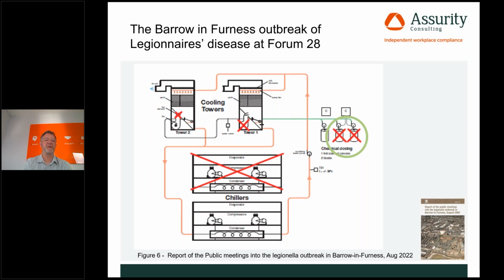As far as the two cooling towers went, on cooling tower number 2 the fan damper on top of one of the fans within the tower had become so badly corroded that it was almost closed and therefore not working effectively. In the other tower, the fan impeller blades - the blades that drive air through the cooling tower with water falling in the opposite direction, cooling it through the latent heat of evaporation - had become so badly corroded that they'd fallen out of the fan and were in the bottom of the pond of the cooling tower.